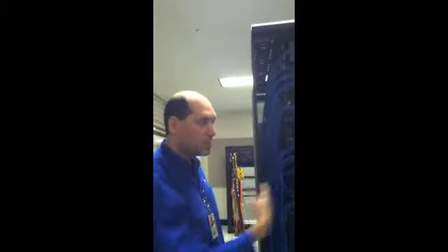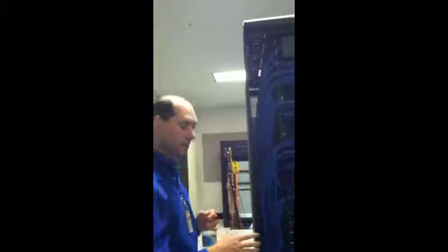This looks pretty nice. You can see labels on every single wire. You need to know where it is going and where it's coming from. If you have a problem on a wire, you need to know which one to replace. Because you're not going to go through 100,000 wires and test each one to figure it out. So we label every one, and we have it very, very tightly laid out to where it comes from, where it goes to, and how it gets routed. I'll show you a little more of that over here.